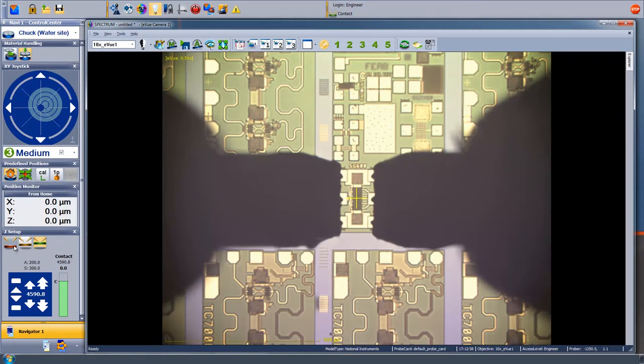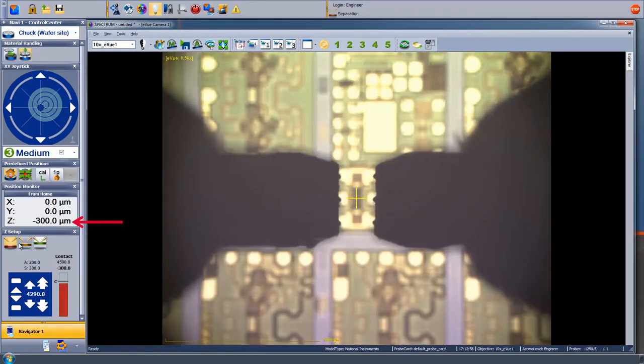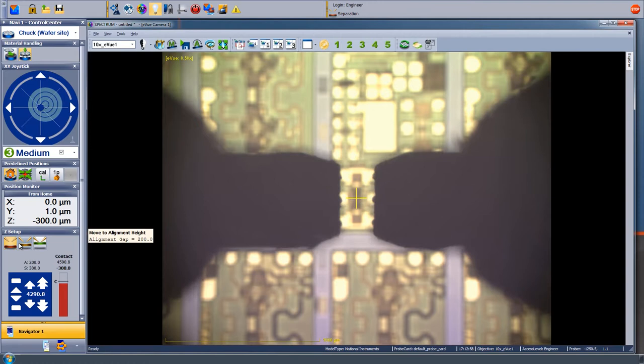To visit this location, we set the chuck for a separation height of 300 microns and raise the probes even further so that the probes are guaranteed not to hit anything as they travel to the ISS site. Using the VeloX interface, we select Go to ISS.